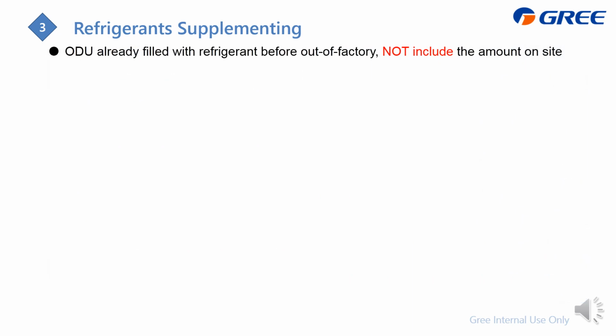As you know, the outdoor unit is already filled with refrigerant before leaving the factory. However, the amount inside the outdoor unit does not include the amount needed on site, because we don't know how many indoor units there are, and we also don't know the details of the piping, right? So on site you need to charge the refrigerant.